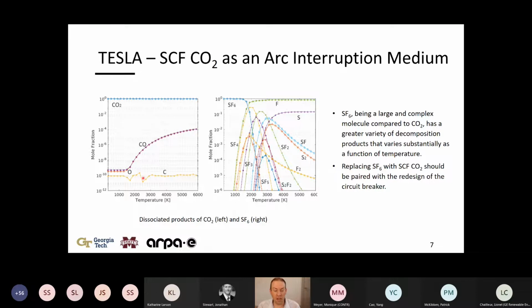Now with carbon dioxide, it actually looks a whole lot better. Over the same temperature range, you see it stays mostly carbon dioxide. As it decomposes, you get small mole fractions of carbon monoxide, oxygen also, obviously, and at the 10 to the power minus 10 ratio, solid carbon. Now the solid carbon obviously is an issue which needs to be addressed because it's conductive, so if that is found on dielectric surfaces, it could potentially be an issue.